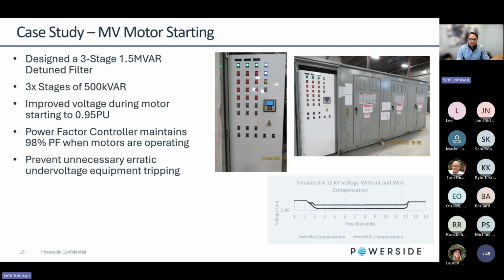So we will go to the solution that we had provided here. What we ended up doing was designing a 1.5 megavar detuned filter. It's in a 3-stage configuration, so 3 stages of 500 kvar. And this is going to be connected, or was connected, with the motor starting sequence of the soft starters. So soft starters would send a signal to our equipment. We would engage a stage or multiple stages depending on the motor starting sequence. And this would improve voltage substantially.